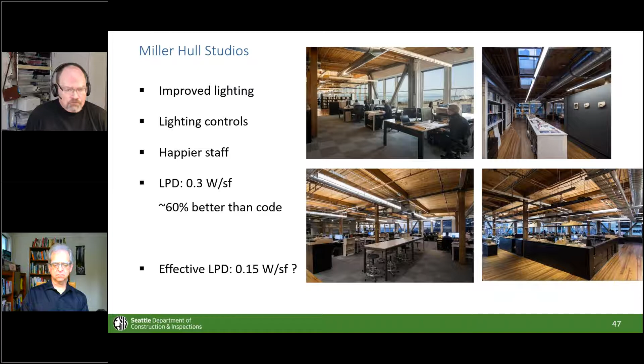So the allowance for an office building is, I think, 0.58 watts per square foot, right, per office building as an aggregate. So we're 60% better than the code here. Now again, this may be something of an outlier. We've got great daylight. We've also got a client that is very, very heavily engaged in sustainability. If we add in the lighting controls, we're actually probably down to an effective lighting power density of about 0.15 watts annualized, something in that range. Could go to the next one.